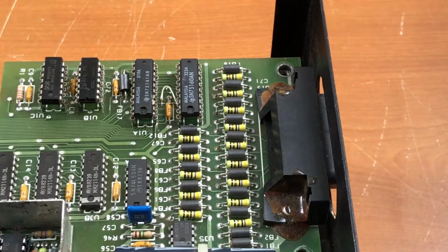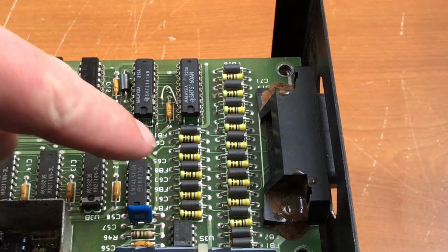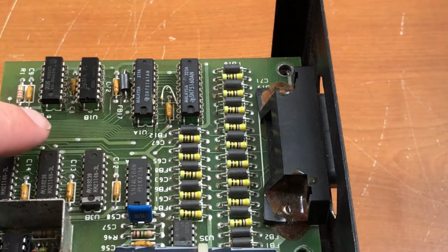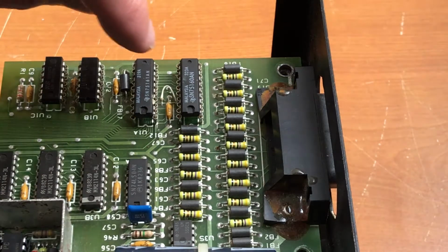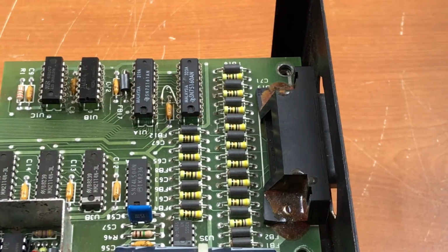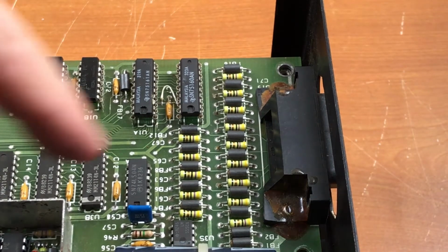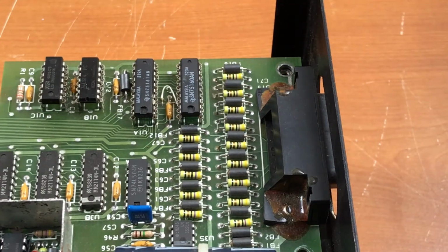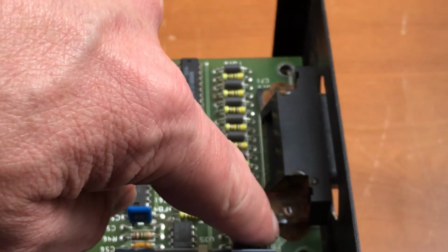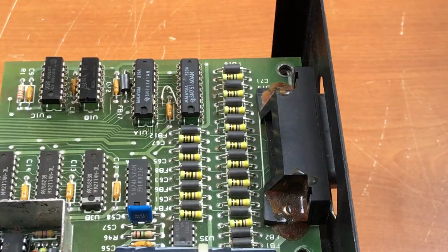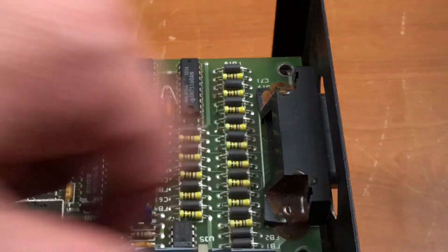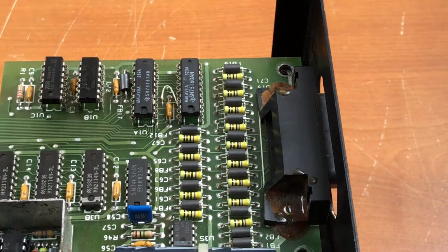Taking a look at the insides, I noticed a few things. Someone had previously done some repairs to this section here. These chips are all socketed, and there's a jumper wire right there, probably a damaged trace when someone removed the chips previously. And unfortunately, this IEEE connector right here looks like it was held in with rivets, and the plastic has split on both sides where that rivet is. So someone has epoxied it back into place, and the nuts that you screw the connector onto are missing.